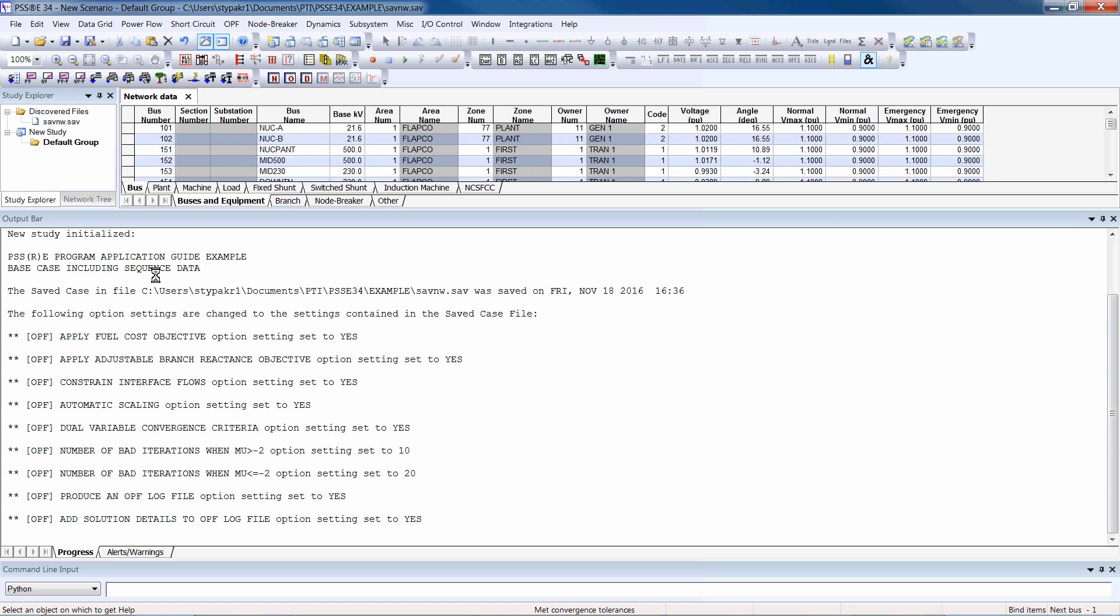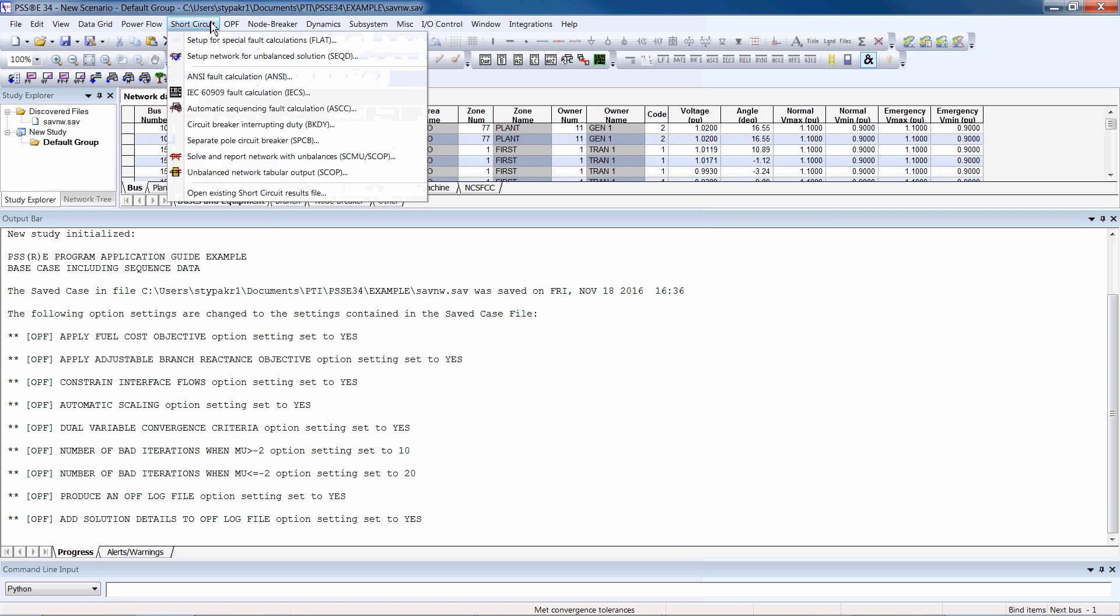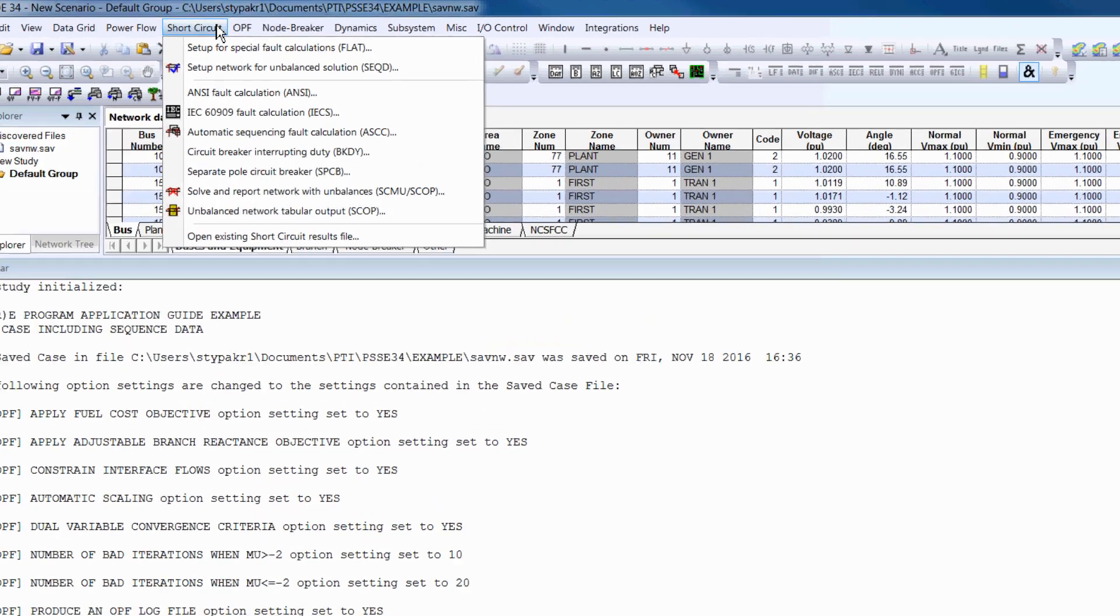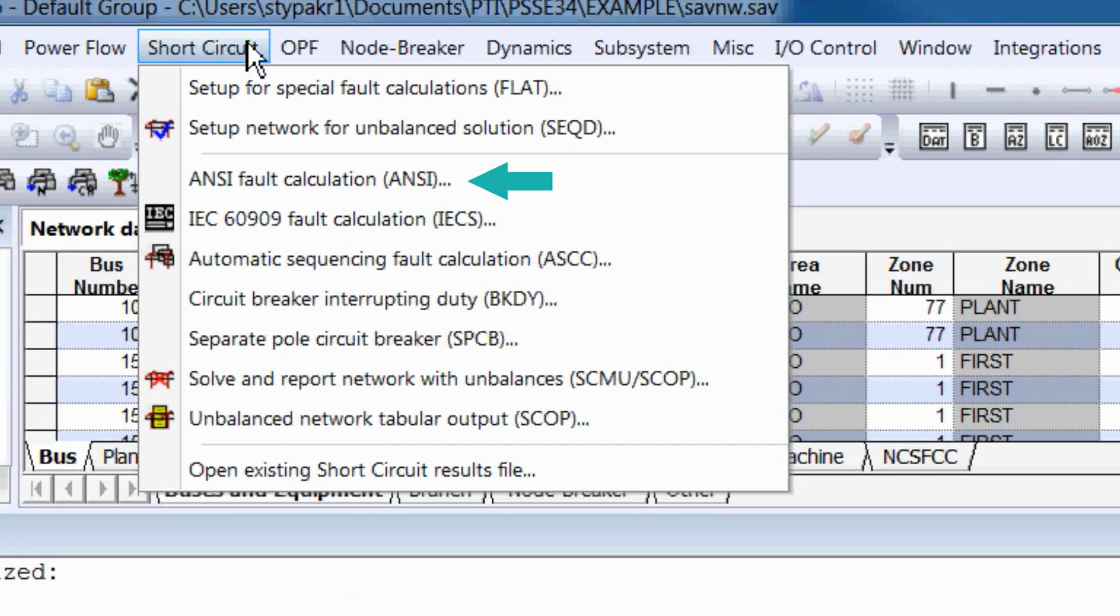To view various short circuit activities, click Short Circuit from the menu. ANSI calculates fault currents based on the IEEE C37.010 standard. IECS calculates fault currents based on the IEC 60909 standard.